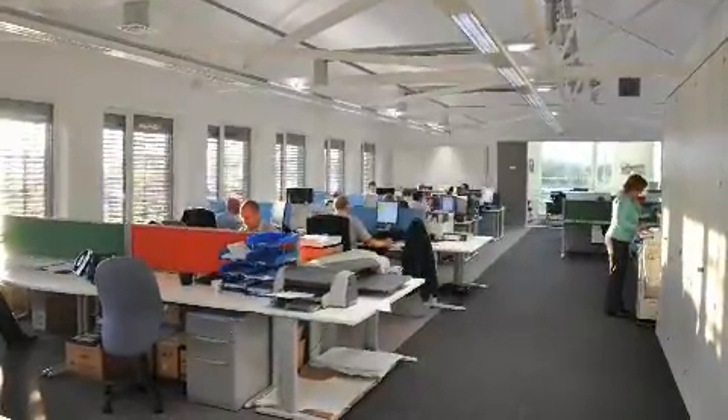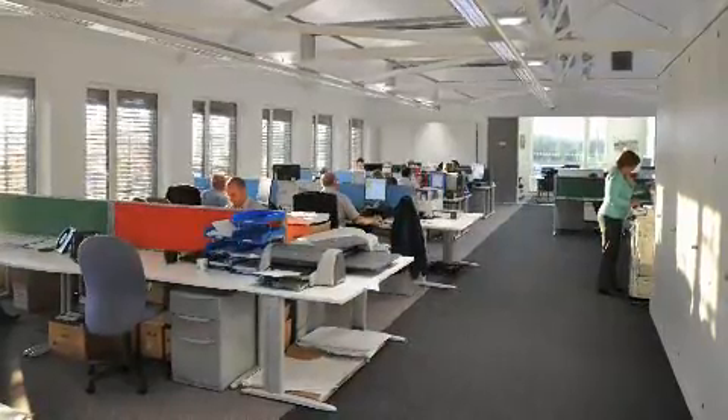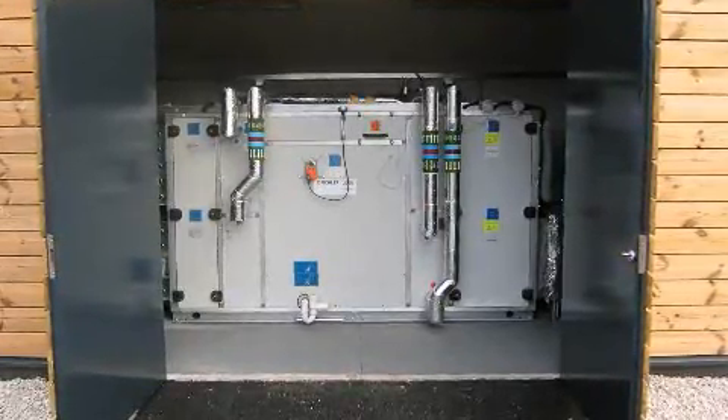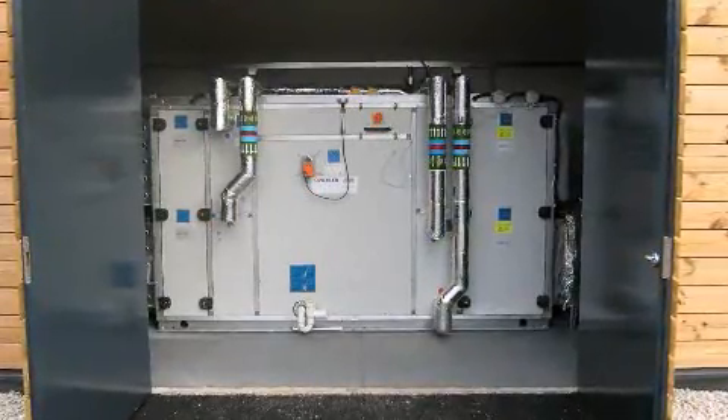In the middle of summer, the air in the tubes acts as cooling, so it's like a free air conditioning plant to a certain extent. When it goes into the heat exchange unit in the air plant down below, there is a plate that can either extract the heat or extract the cold out of it. The air which is being recycled is evacuated out of the building, but it's had the heat removed from it before it goes out, and it's something like 85% efficient in the extraction of that heat. So we need very, very little heat to heat the building.